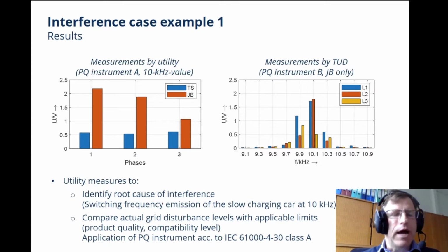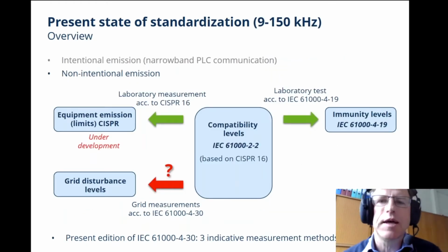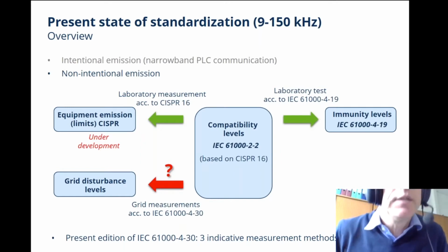This might really be misleading, especially when it comes to the second challenge for the utility: comparing actual grid levels with applicable limits, like compatibility levels or product quality values in 50160. On the left side it was a power quality instrument class A, but the method that has been implemented is not a normative one.